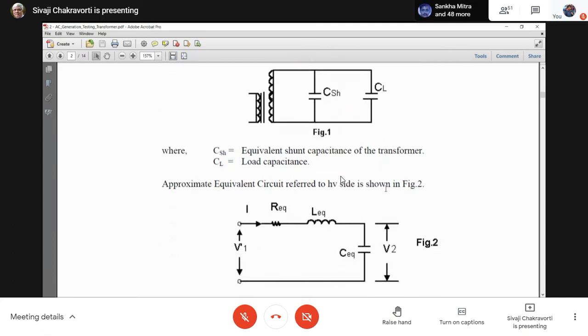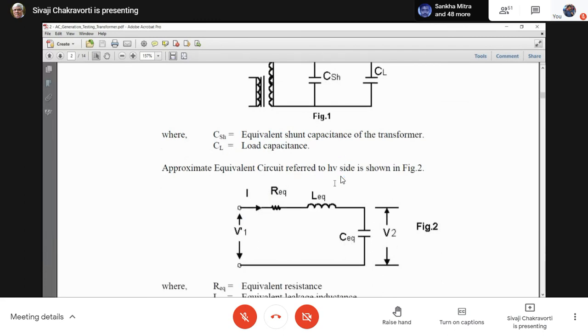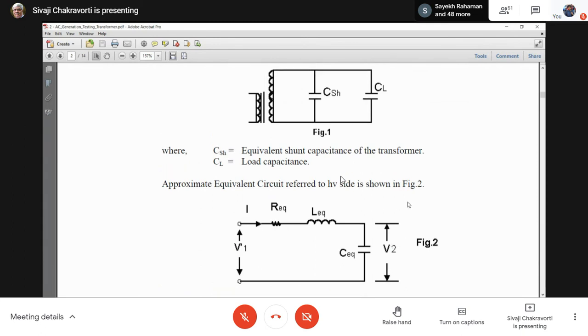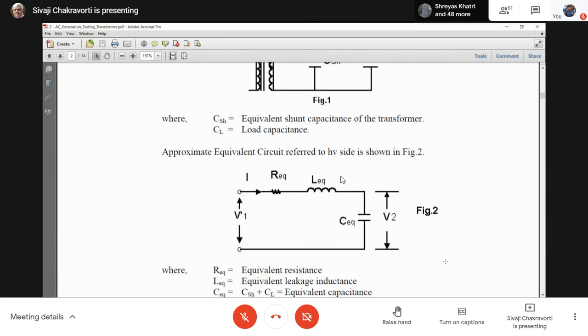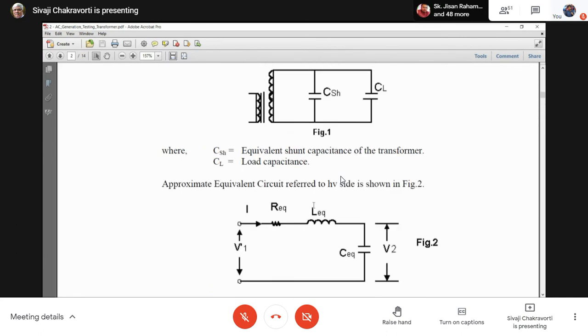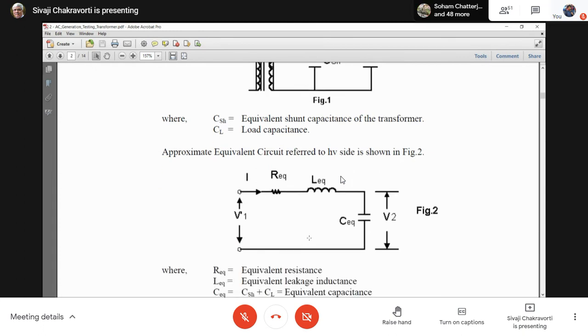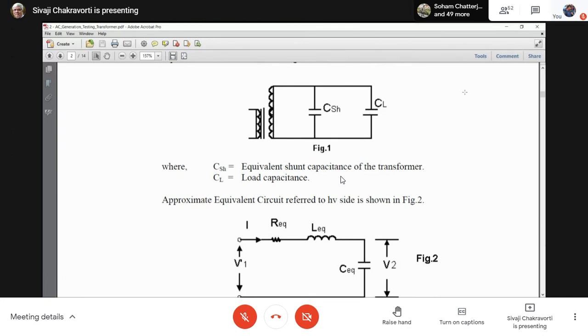Even though it is low, it is there. So therefore, what is the equivalent circuit? This is the series short circuit impedance of the transformer, the equivalent resistance and equivalent inductance, which you all know how to do. Then the equivalent capacitance, which is a parallel combination of CSH and CL. This is here. And then this V1 prime is the transformer end voltage referred to the high voltage side. That means not referred to the low voltage side of Figure 1, but referred to the high voltage side.